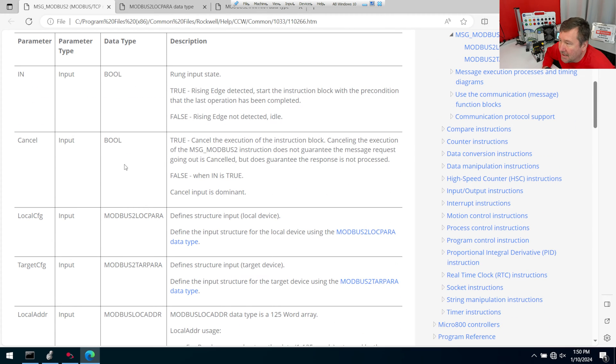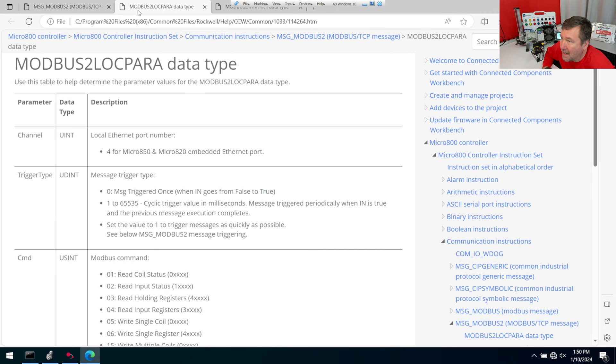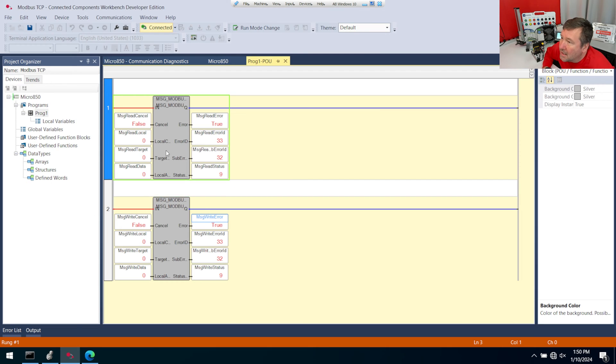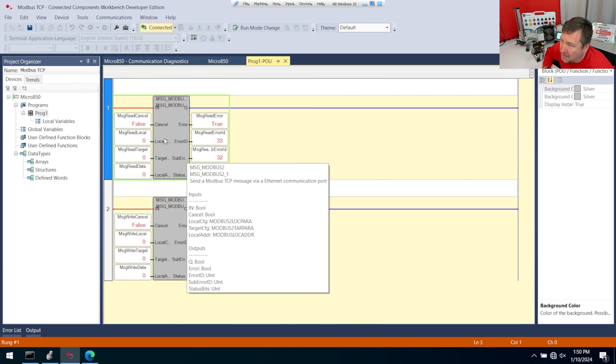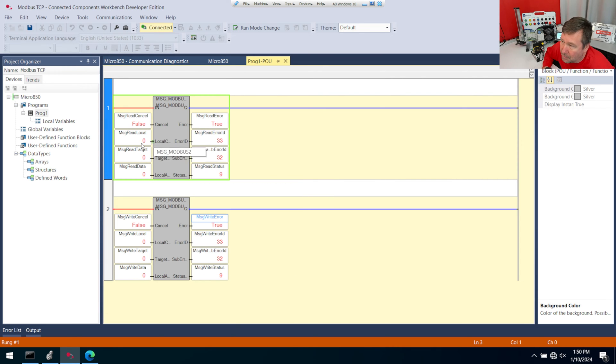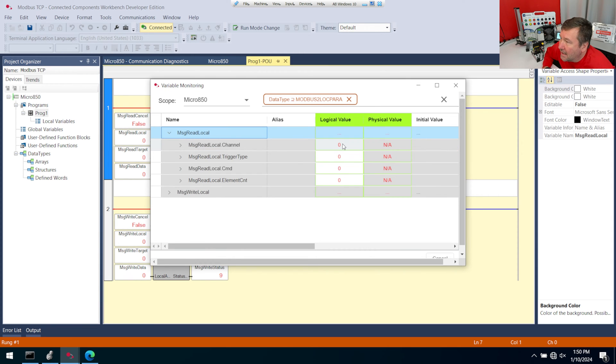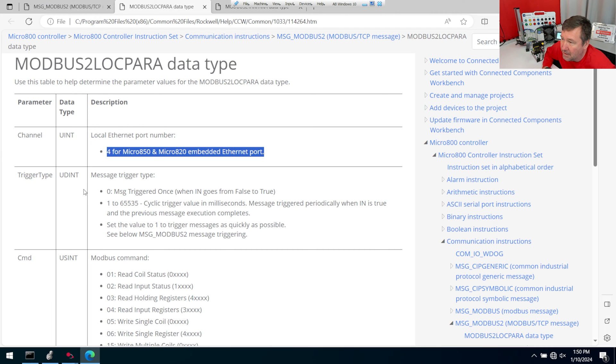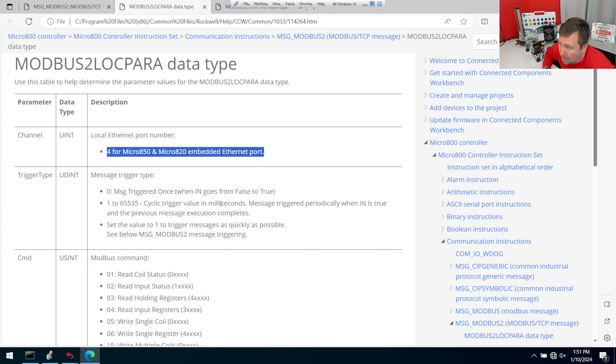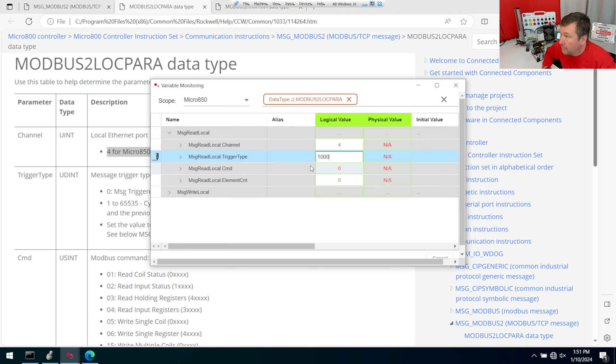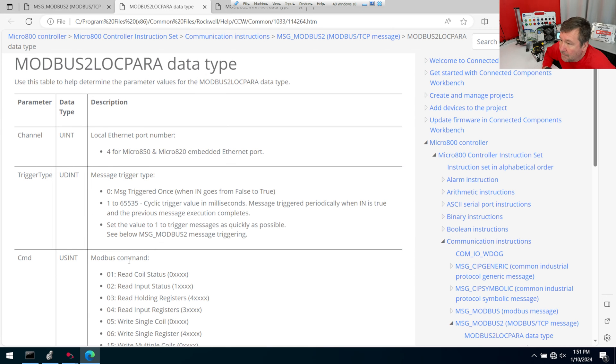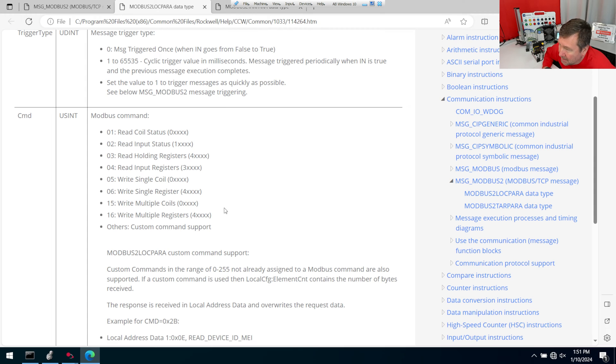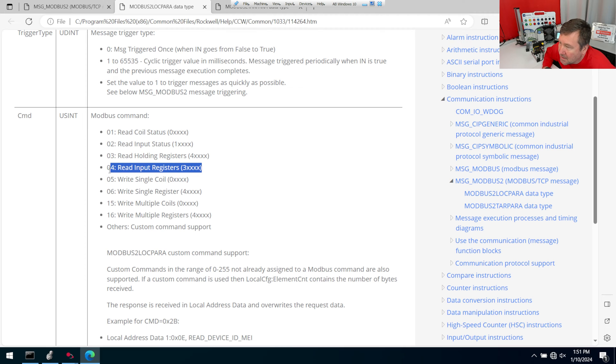And the first thing we're going to need to figure out is this local config here. That's the first tab we opened up. And the first thing we need is to set the channel number to 4 because that's always the Ethernet port. So we're going to double-click. And we're just going to focus on the read right now because if you can get one to read, you can figure out the write. There could be a little more difficulty to the write. So I'll open up my local read and I will set my channel to 4. And now let's go back over here. And the next thing we have is our trigger type. So if we have it set to 0 as we do right now, it's only going to trigger when it makes a false to true transition. If we put a value in here, though, it's actually going to cycle every so often. So I'm going to set this to 1,000 milliseconds, which will be 1 second.